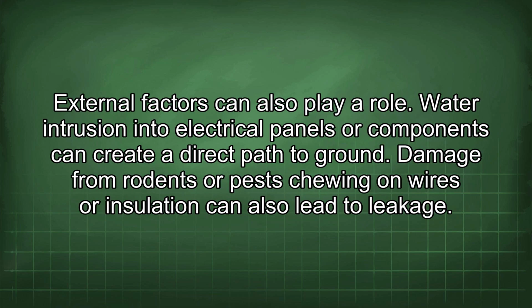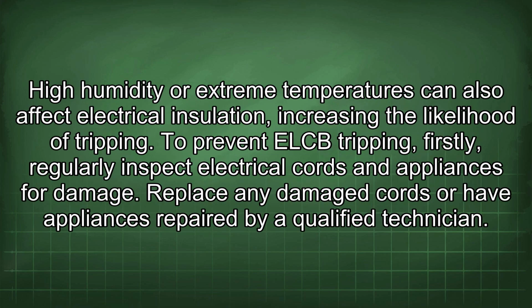External factors can also play a role. Water intrusion into electrical panels or components can create a direct path to ground. Damage from rodents or pests chewing on wires or insulation can also lead to leakage. High humidity or extreme temperatures can also affect electrical insulation, increasing the likelihood of tripping.